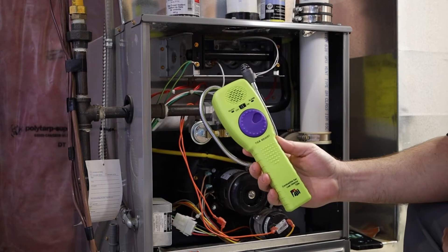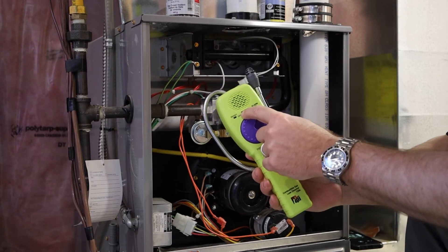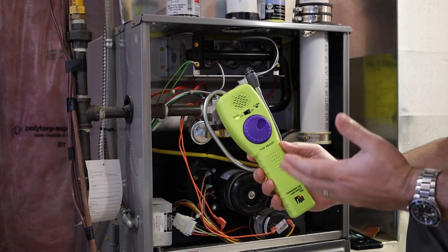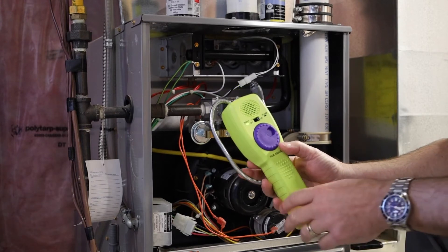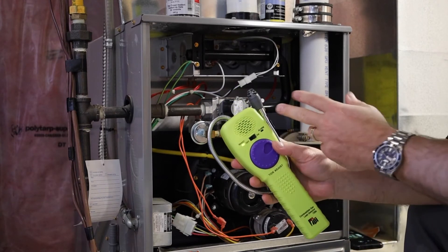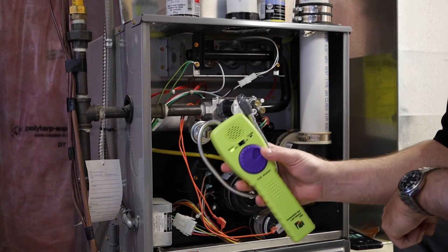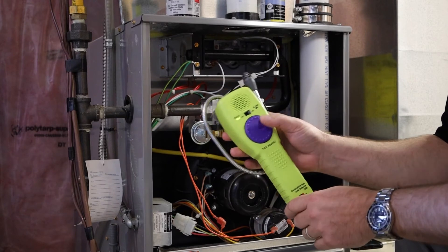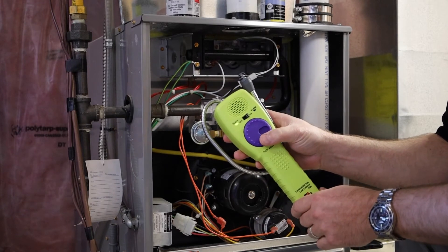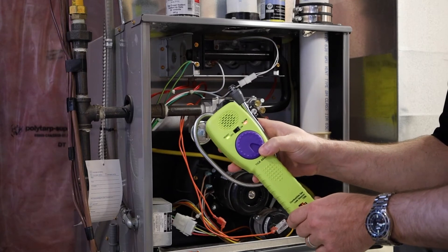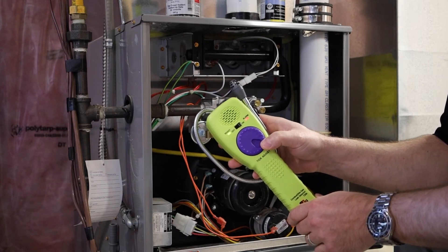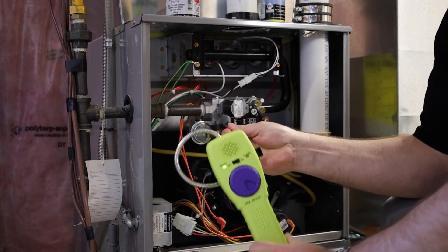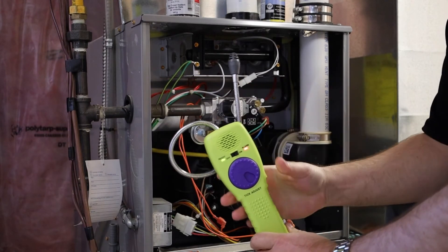The next one is the 720B. You can slide it on there. Again it's going to take 30 seconds, a minute, even longer on colder weather. You know if this thing's been sitting out in the truck and today it's about minus 15 this morning. It's got a thumb wheel, instead of on the side it's on the front. So there you can tune it out. So again you want to get the steady tick rate. Go towards your gas sample and there it is.